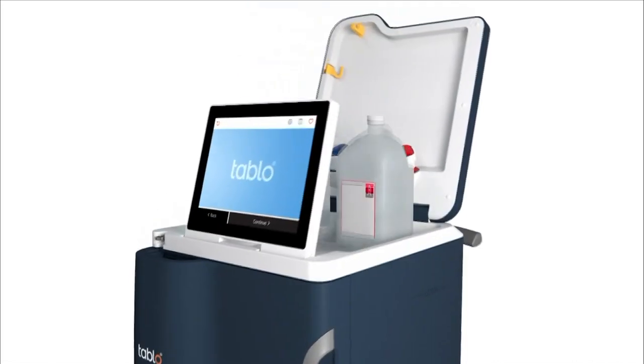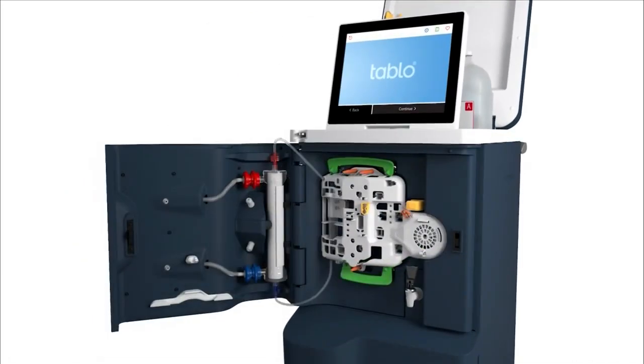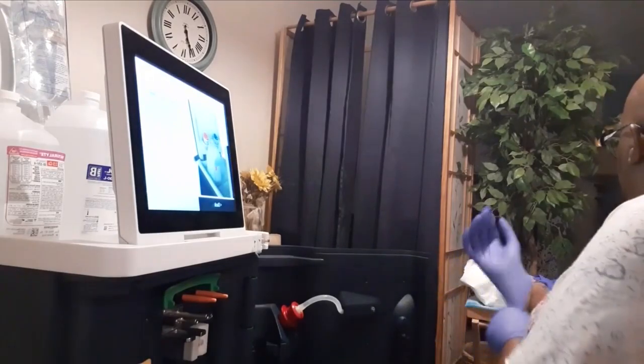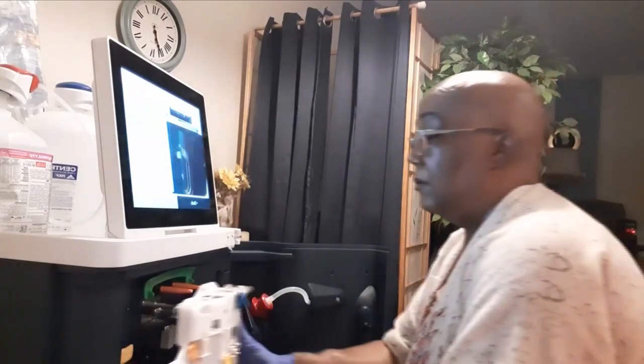This time, Tracy had a new option. She is the first in the U.S. to use a new portable home dialysis system called the Tablo. Patients are trained to use the machine, hooking themselves up through a connection in an arm vein called a fistula. The patient would then insert two needles into that fistula to get the blood to the machine so that it can remove excess water and clean the blood.